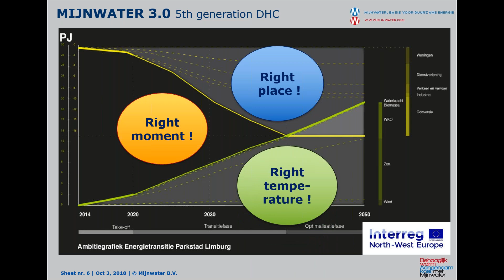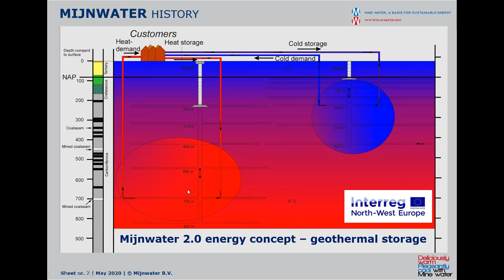When we looked at Mijnwater and these mines, there is a lot of energy in there, but it's still a limited resource. That brought us to the 5th generation district heating grid, where we try to make the grid on the ground in the city more intelligent and smarter, to use this energy better. About 10 years ago we switched from just taking heat and cold from the earth to also using it as storage. So we made the hot bubble, where we take energy in winter time and re-inject it in summer, and the cold bubble, where we take cooling in summer and re-inject it in winter. We don't need a return well anymore, because now we have bidirectional sources where we can take and return water at the same point.